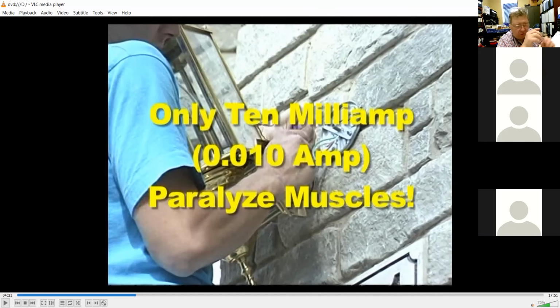Now, do y'all wonder why the breaker did not trip? Has anybody thought about that? Why didn't the breaker trip? Here's kind of what evidently happened. The jacket on that cord got damaged, but you didn't have a hot wire shorted to neutral, and you didn't have a hot wire shorted to ground. You didn't have either one of those, huh? It was just the hot wire, the one that was cut. So it was only the hot wire that was cut, exposed, and you didn't have a short circuit condition that could trip a breaker. But yet you had an exposed conductor that got you, and then when it hit you, it went through your body and it went to ground.